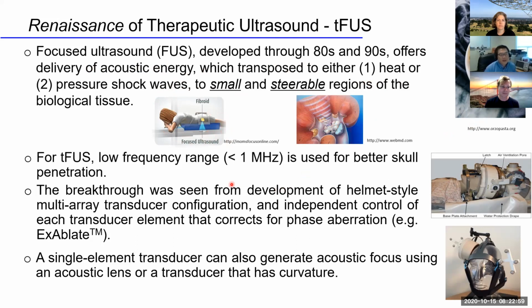For transcranial application of FUS, a low frequency range, typically less than 1 megahertz, is used for better skull penetration. I believe the previous lectures have discussed the rationale behind using the lower frequency compared to the one used in diagnostic ultrasound imaging. The breakthrough was seen from the development of a helmet-style multi-array transducer configuration and independent control of each transducer element that corrects for the phase aberration, and MRI guidance is used in conjunction with the configuration in order to place the focus onto the desired location of the brain.